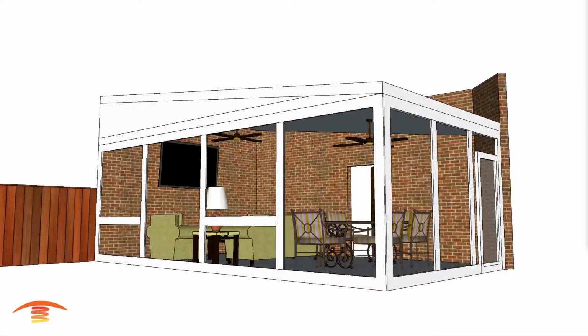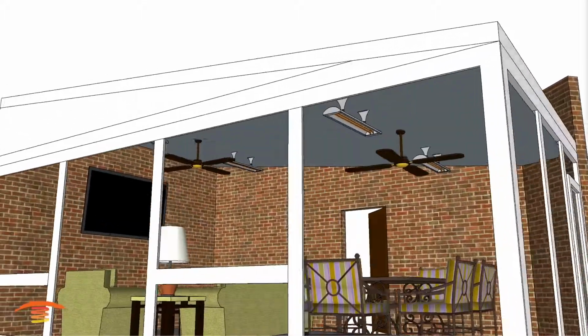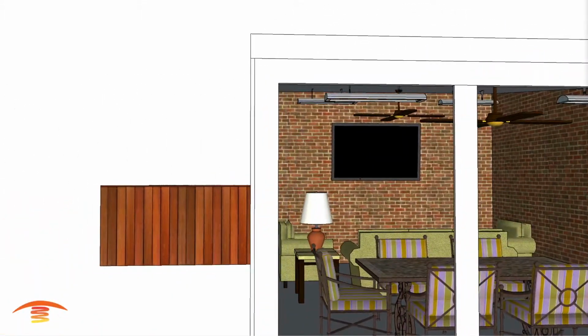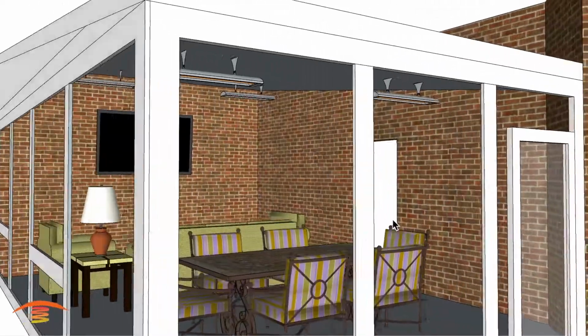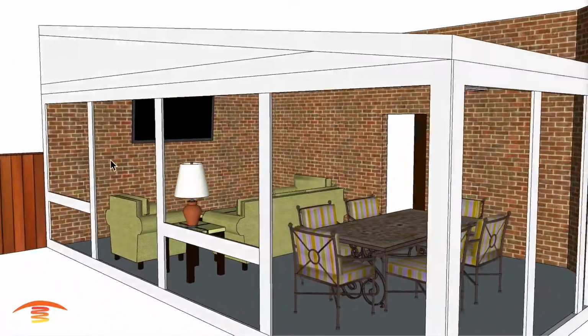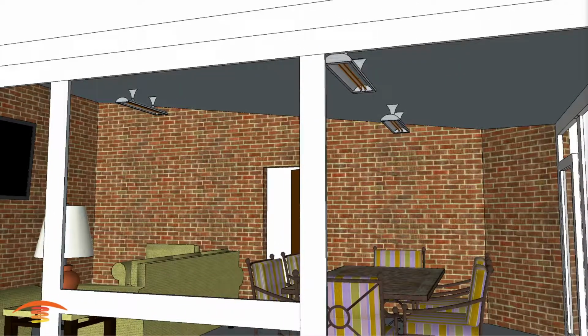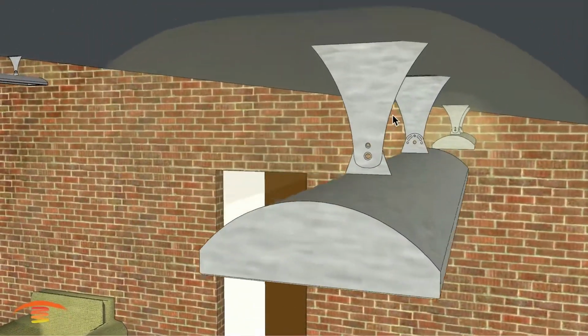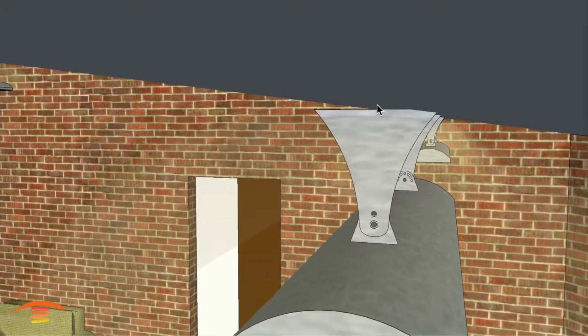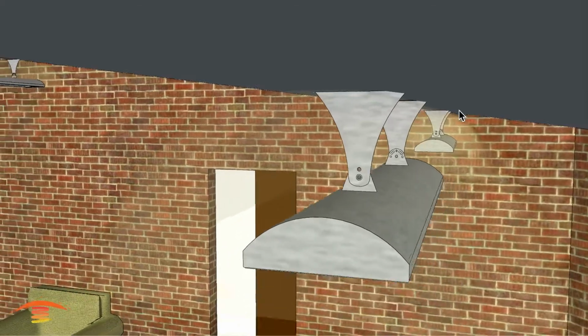and we will look at one final option, which would be possibly using it in this fashion without a fan. Maybe again a light is in there, but this is going parallel with the table here and parallel with this wall over here, and you can see that all things still need to be met as far as clearances. So there's no issue with clearances, and you're going to attach the brackets to the ceiling, and they'd have to mimic the slope of the ceiling.